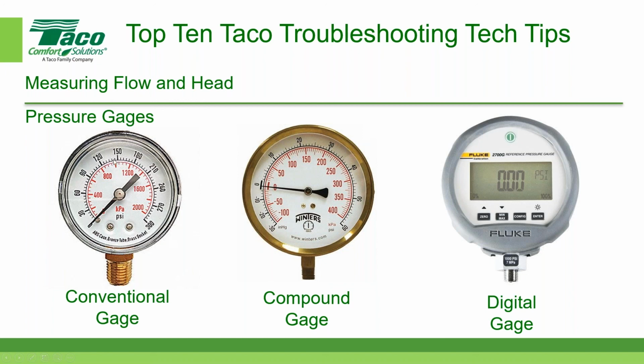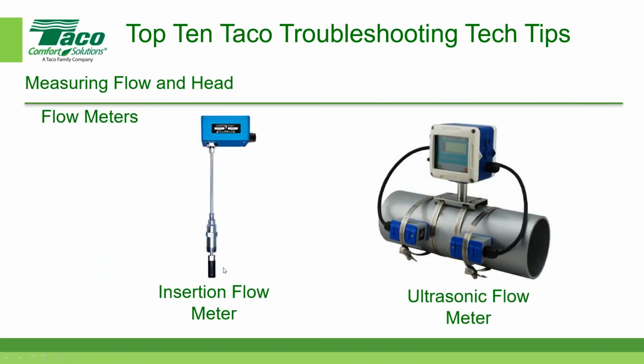And that would be much more accurate, to have a gauge that's reading it at mid-range than it is way down here. They lose their accuracy down here. So try to select gauges that are appropriate for the pressures that are being read.